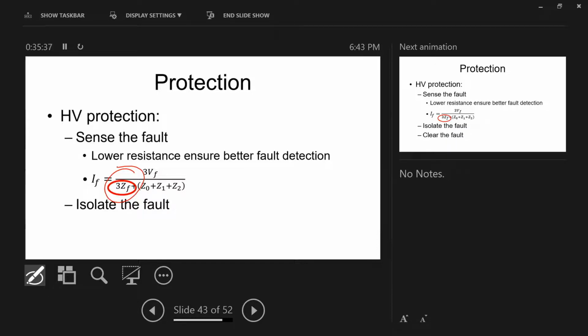Now, after I needed to sense the fault, I needed to isolate the fault. Why do I need to isolate the fault? Guys, the heat element that causes explosion is I squared R. When I increase this current, it's very huge, maybe 10 or 20 times the rated current. All the equipment, if you look at your circuit breaker, your transformer, is designed for additional current for a short period: 2, 3 seconds, 5 seconds, 1 minute. So what I have to do is isolate the fault in a very clear and fast way.